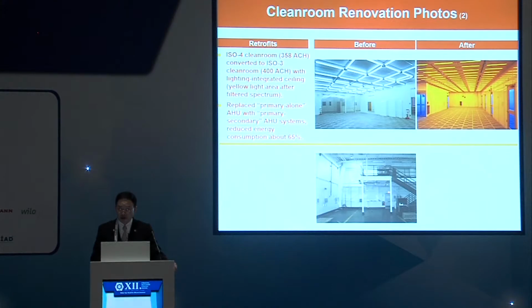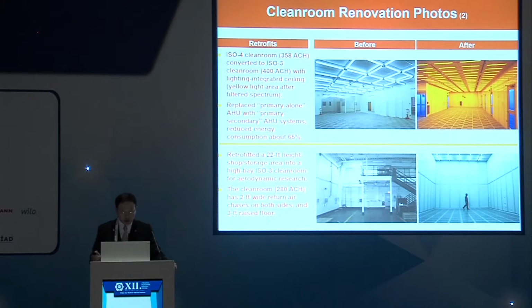This used to be a warehouse. After renovation, it became a clean room. And it's a 22-foot retrofit space to be an ISO 3 class high bay clean room. And on the left and right sides, these are the common return chases. Return chase on each side, this is the raised floor, where the return air goes through the perforated floor, then back to the return chase, then is dropped by the fan into the ceiling space.